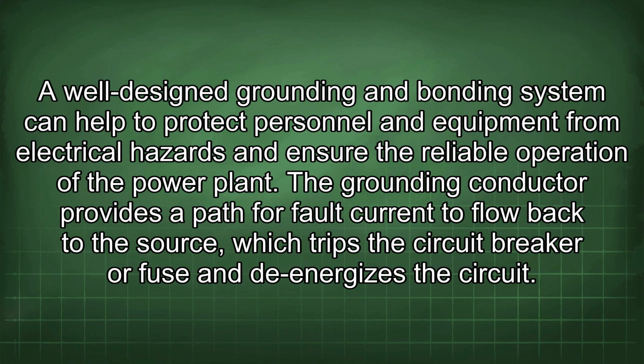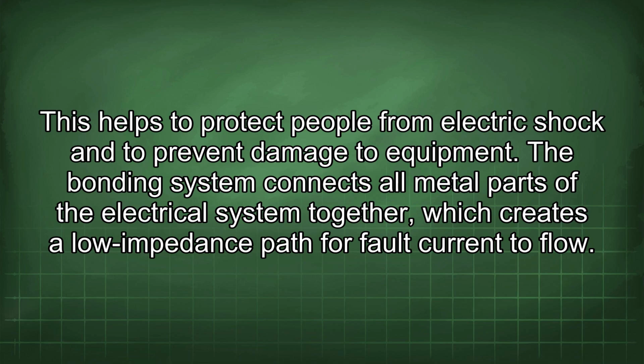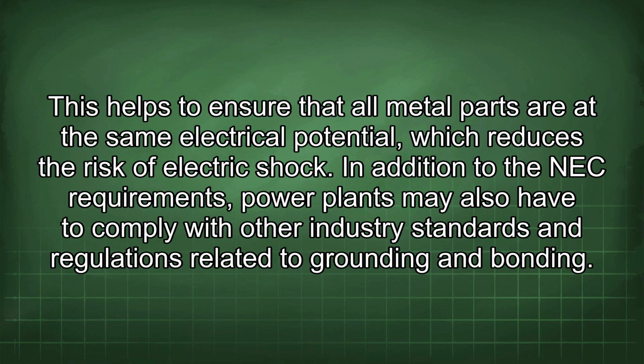The grounding conductor provides a path for fault current to flow back to the source, which trips the circuit breaker or fuse and de-energizes the circuit. This helps to protect people from electric shock and to prevent damage to equipment. The bonding system connects all metal parts of the electrical system together, which creates a low impedance path for fault current to flow. This helps to ensure that all metal parts are at the same electrical potential, which reduces the risk of electric shock. In addition to the NEC requirements, power plants may also have to comply with other industry standards and regulations related to grounding and bonding.